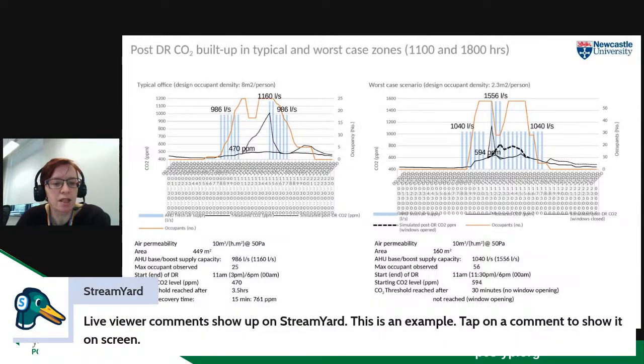And then we modelled turning the air handling units off. So the blue bars show when the air handling units are on. So they're on in the morning, and then we modelled switching them off over lunchtime. And we looked at the response in terms of CO2 in parts per million, which is the black line. And so whilst there's no blue bars, the carbon dioxide level creeps up. And once it hits 1,000 parts per million, then you can't override the air handling unit anymore. It comes on in order to reduce the parts per million back down. So for the typical office, we didn't reach that 1,000 parts per million until the air handling unit had been off for 3.5 hours.